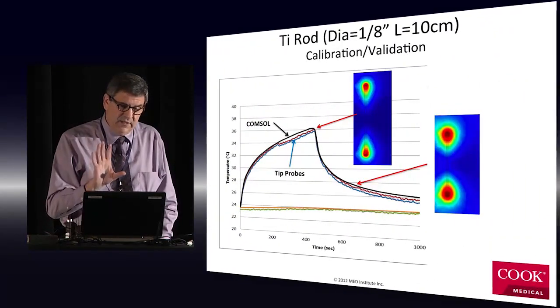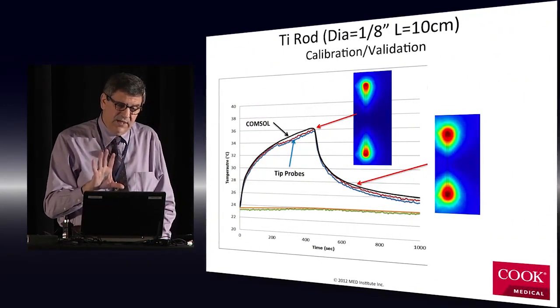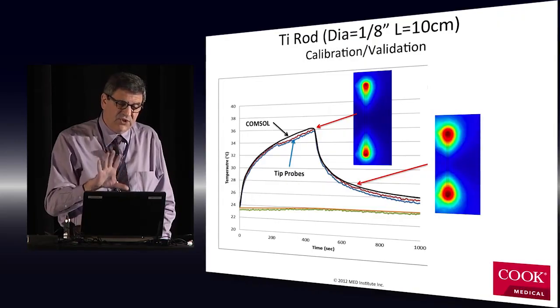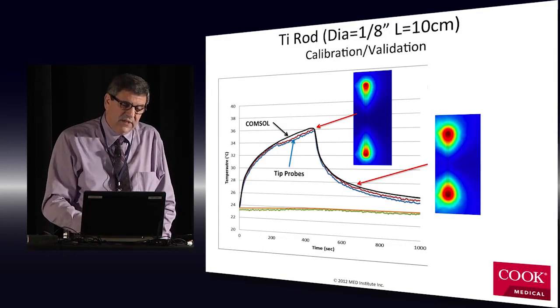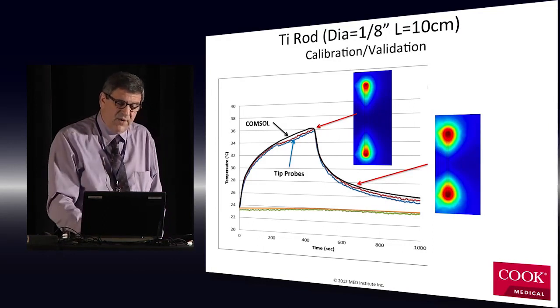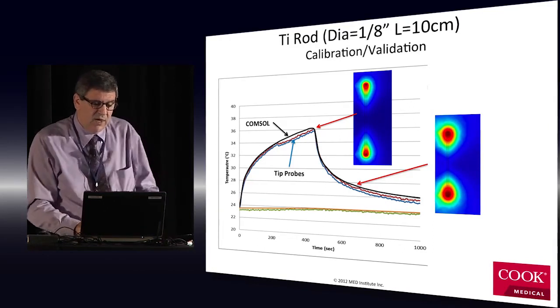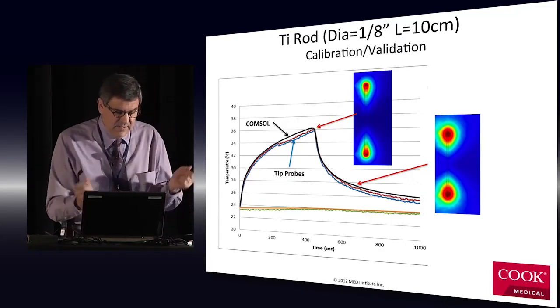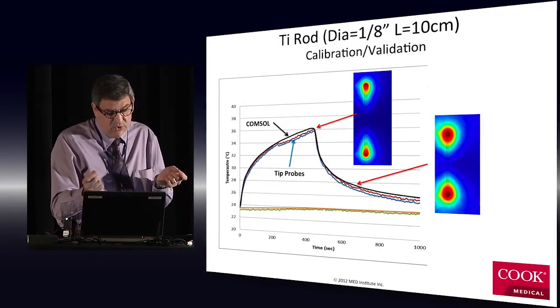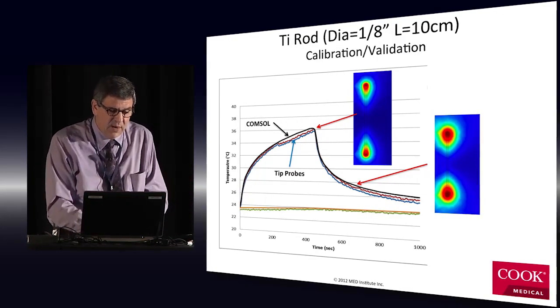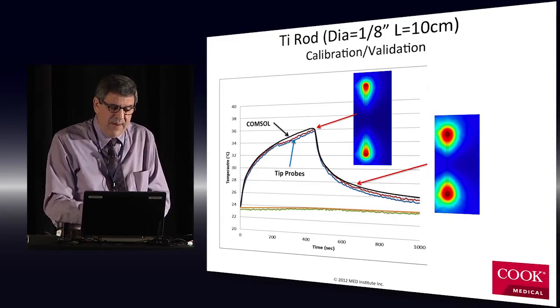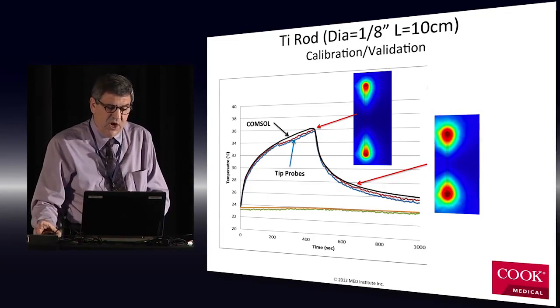So we take something called a titanium rod, 1/8 of an inch in diameter, 10 centimeters long, a calibration rod. Ironically, it's called a calibration rod, and we put this into our ASTM phantom and actually drilled holes in the tip, put in our thermocouples, and we power a test where the coil on time is 450 seconds, and then we turn the coil off and the thing cools down.